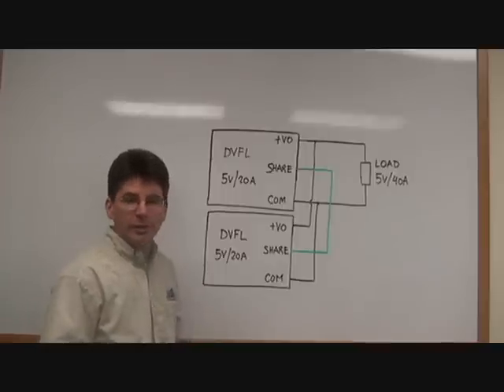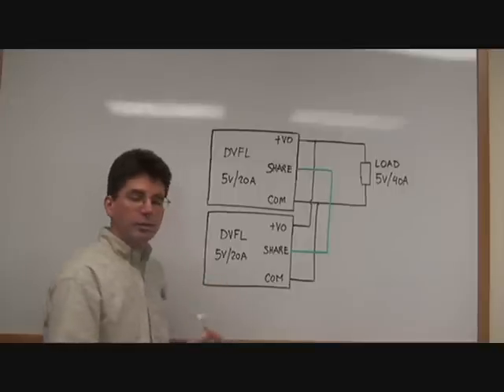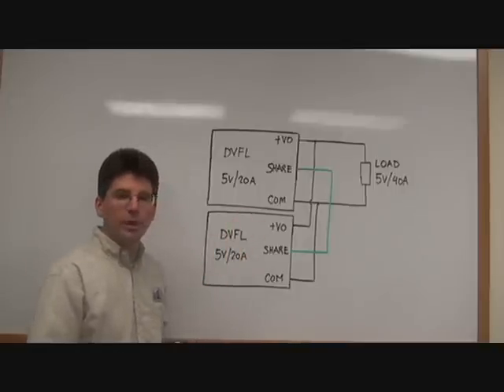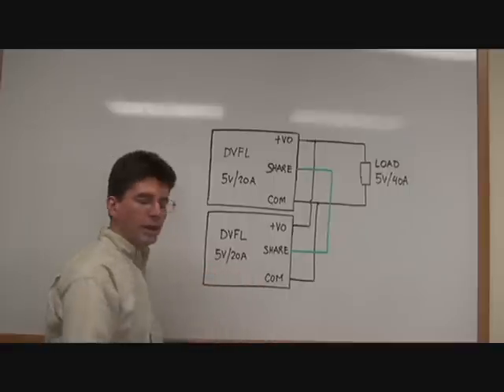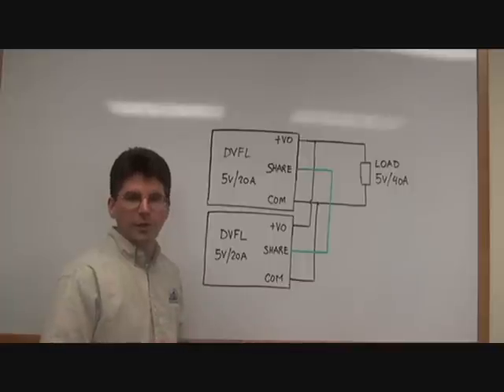The share line itself is fault tolerant, so in a redundant case or in a case where you don't require 40 amps, one module could fail and would not force some kind of system failure.